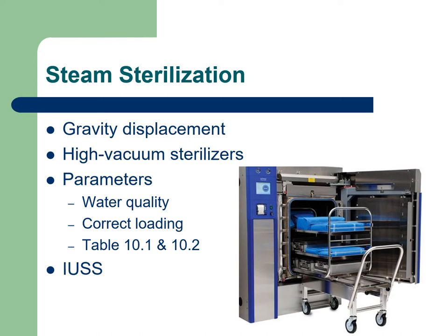Parameters for steam sterilization include time, temperature, pressure, and also water quality. During steam sterilization, we want to use water that doesn't have a lot of minerals in it. If there are a lot of minerals in the water, that can stain and corrode the instruments, making spots on them and making them more difficult to use. There can become deposits on the surgical instruments that impair their function, and that can be costly for the facility.